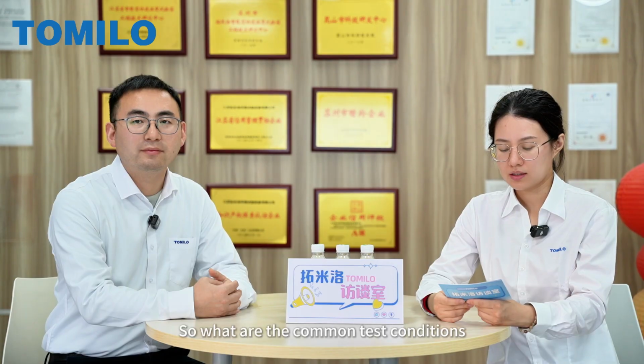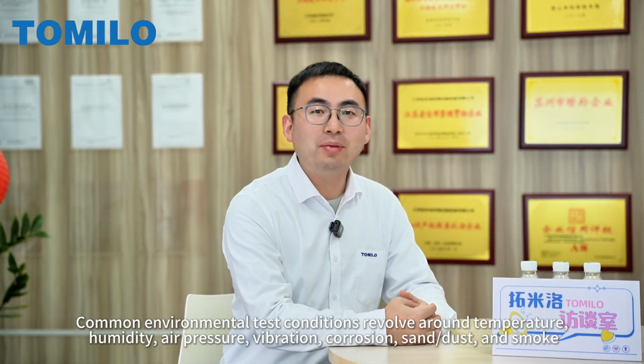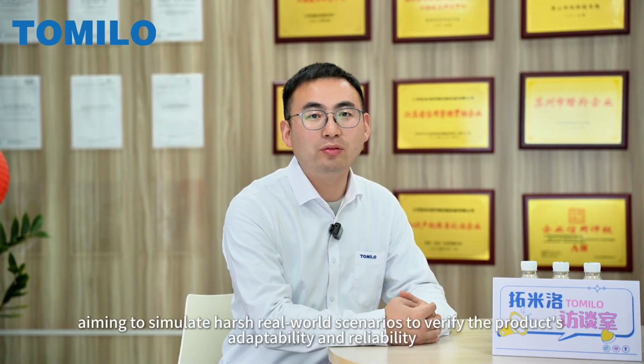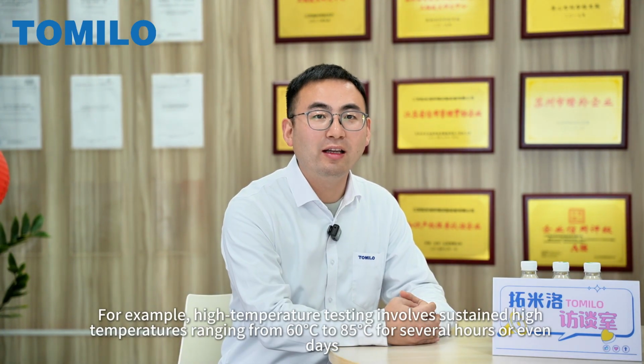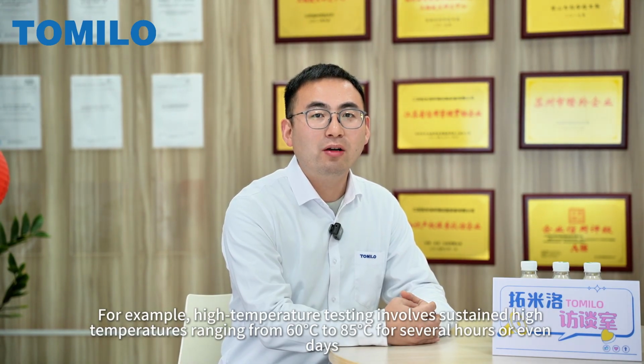That's quite a range of test objects. So what are the common test conditions? Common environmental test conditions revolve around temperature, humidity, air pressure, vibration, corrosion, sand or dust, and smoke, aiming to simulate harsh real-world scenarios to verify the product's adaptability and reliability. For example, high-temperature testing involves sustained high temperatures ranging from 60 to 85 degrees Celsius for several hours or even days.